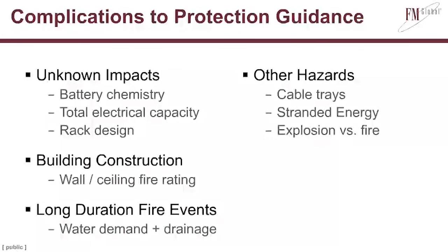There are also other hazards that I didn't specifically address in these tests. The first one is cable trays. Especially if you have multiple energy storage systems together, you'll have transmission cables. I've seen a lot of installations where these run above the top of the rack, so maybe that's an obstruction between the sprinklers and the rack. It may also be additional combustible loading. The systems I tested could be 700 to 1,000 volts, so you have a Class C fire there.